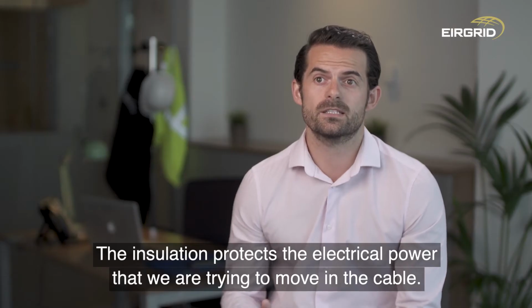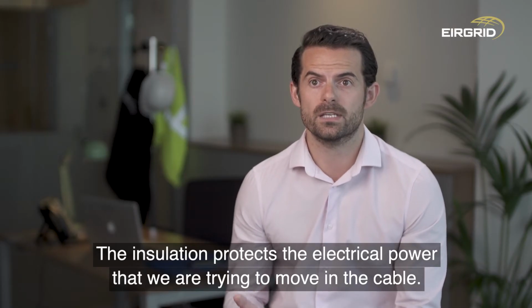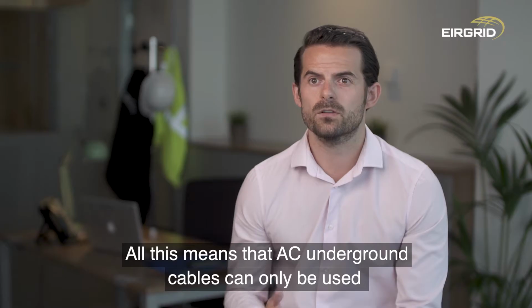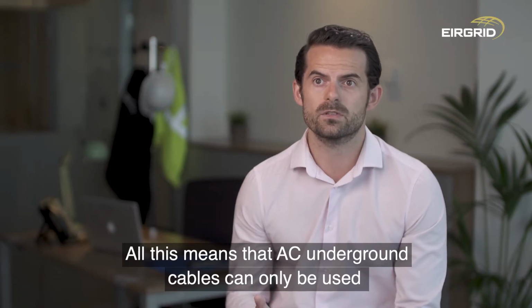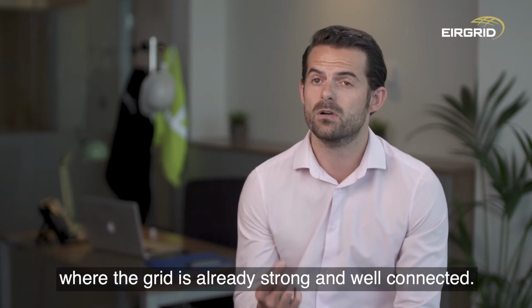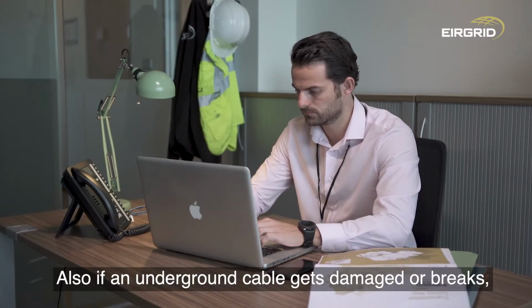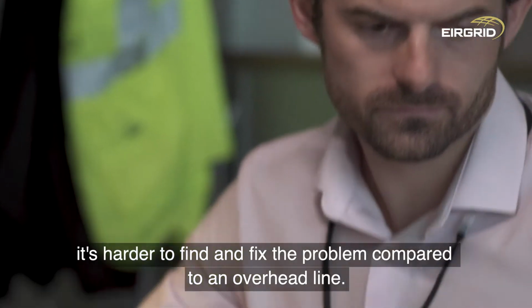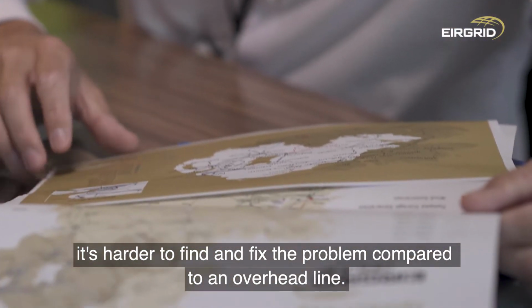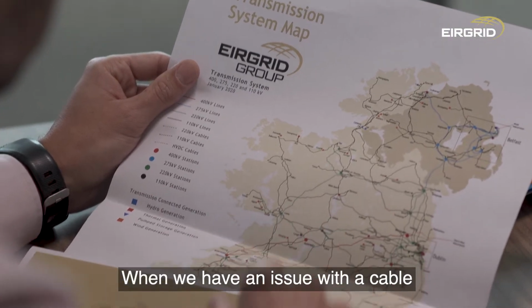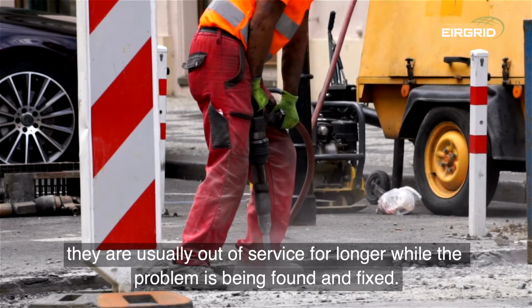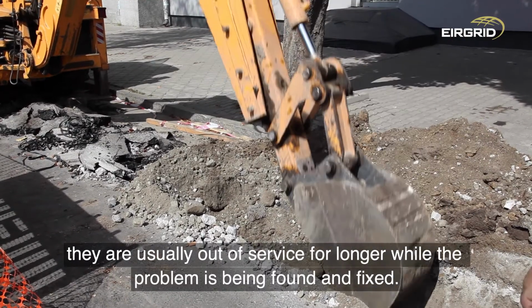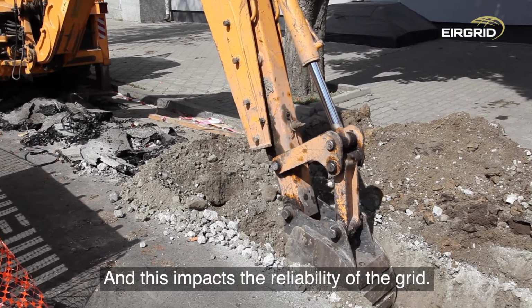The insulation protects the electrical power that we are trying to move in the cable, but it also builds up the energy. All this means that AC underground cables can only be used where the grid is already strong and well connected. Also, if an underground cable gets damaged or breaks, it's harder to find and fix the problem compared to an overhead line. When we have an issue with a cable, they are usually out of service for longer while the problem is being found and fixed, and this impacts the reliability of the grid.